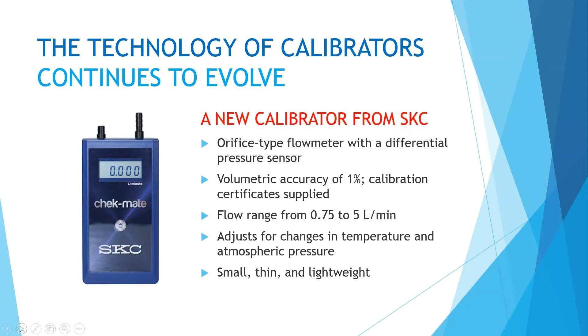Now, one of the most common questions that I get on this new calibrator is whether it calculates an average. The simple answer is yes, but let me tell you more. Other electronic calibrators take a series of single discrete readings. The bubble or the piston goes up the chamber, possibly with an added kerplunk, kerplunk, to tell you it's taken one reading. Depending on how many readings you want, it will then take an average at the end of all of the single readings. The Chek-mate instead displays a moving average of the measured flow rate.